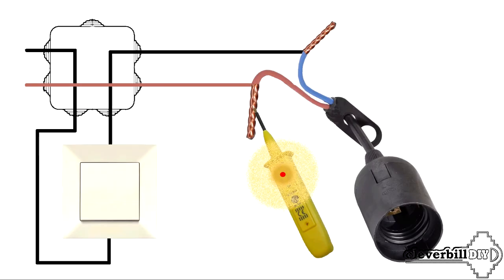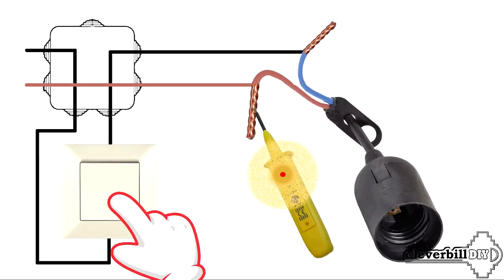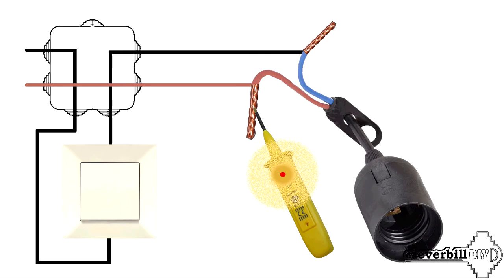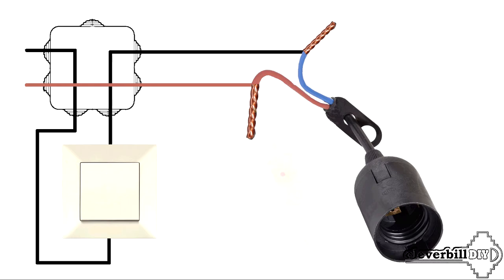If on the wire coming out of the ceiling, regardless of the position of the switch, there is a phase all the time, this is bad. Perhaps a mistake was made when connecting the wall switch, in which, instead of breaking the phase by the switch, the neutral wire going to the chandelier was broken.